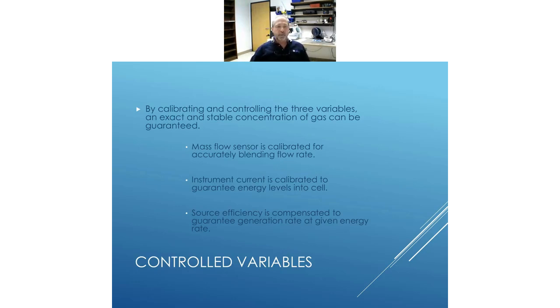By calibrating and controlling these three variables, an exact stable concentration can be guaranteed. To assure that we're giving you exact calibration quantities of the ozone, chlorine, and chlorine dioxide gases we're talking about today, the instruments themselves have a built-in mass flow sensor. As we know, air density changes with temperature and atmospheric pressure. The air density at sea level versus here in Tucson in the United States, at 3,500 feet, is different. So if we generate X amount of molecules of a gas here, it's different than at sea level. These mass flow controllers and sensors ensure that we're always blending the right amount of carrier gas with the right amount of, in this case, chlorine, ozone, or chlorine dioxide.